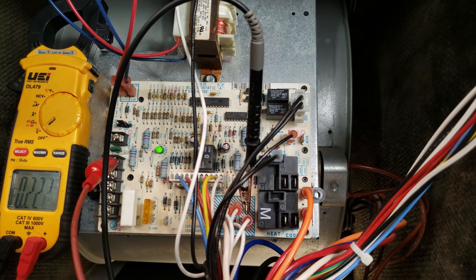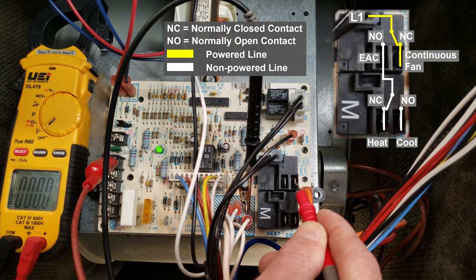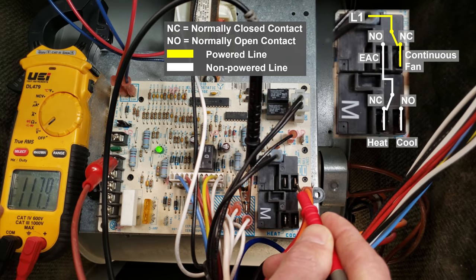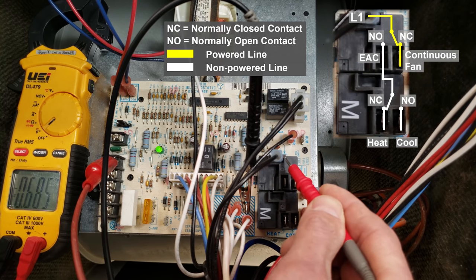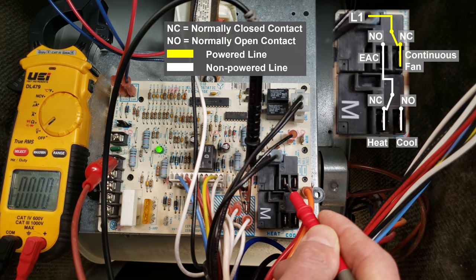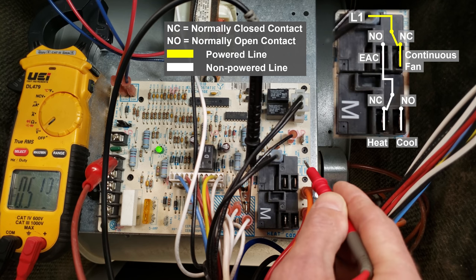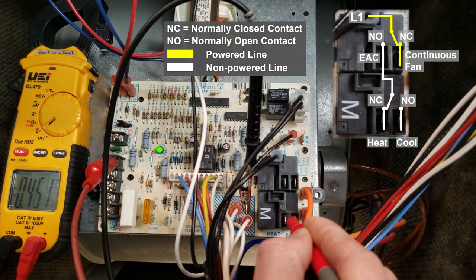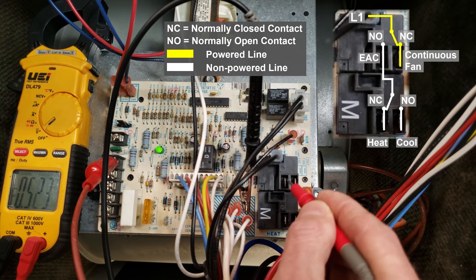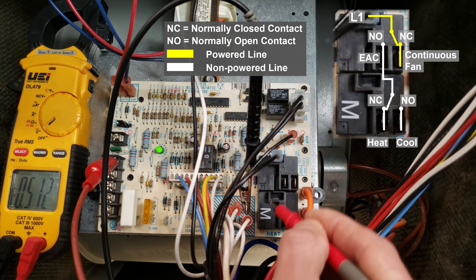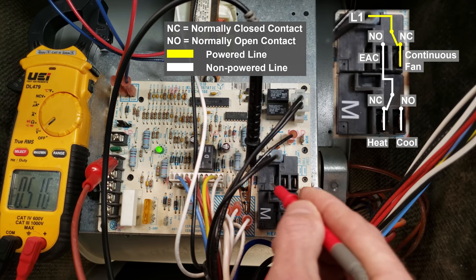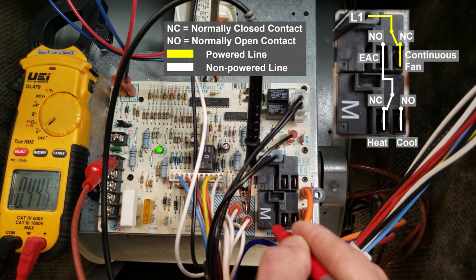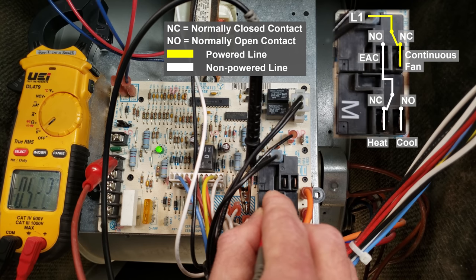First, anytime you have power to the control board you're going to have power over to the continuous fan. So we're reading 117.9 volts, that means from your main power in on L1 it's connected right over to here and we have no power on the EAC. If we have no power on the EAC then we have no power to this second switch down here because this terminal and this terminal are connected on the back of the board. Anytime you see these side by side, this is basically the switch to turn the blower motor on in general, and then it's a matter of if this switch is powered or not which of these two terminals is connected.